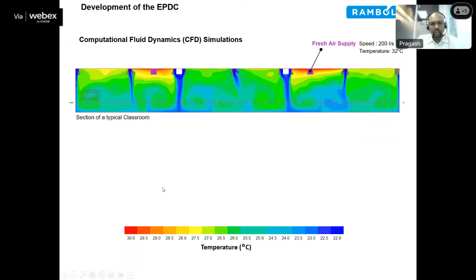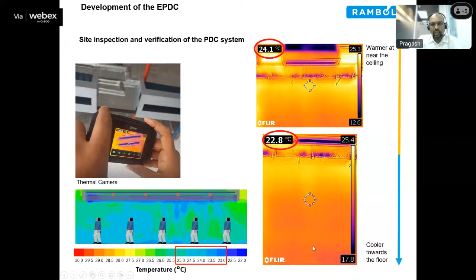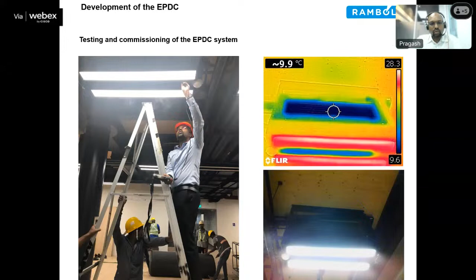The simulation is a simulation, so we verified it with a thermal camera and other tools to ensure that what we simulated is how it works on site. You can see that at the occupied level the space is cooler than the ceiling level in the real project. So we tested the outflow temperature from the coil and the air velocity, all tested. And we achieve the benefits of energy efficiency and uniform airflow. That's more important because in a conventional system, people sitting below the diffusers feel very cold because the air speed is very high, and a bit away from the diffusers it is slow.